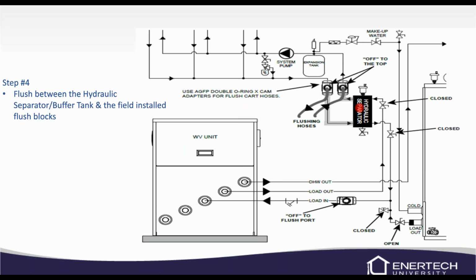Next, we're going to flush on the other side of our hydraulic separator and your flush blocks. This shouldn't take real long either, but from your flush cart out to the flush block, and we're going to be in reverse flow on this here and back.